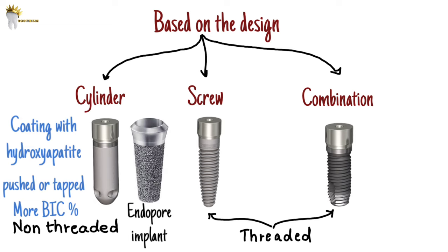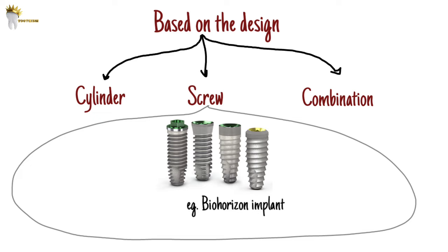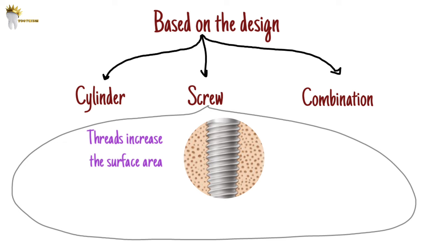The screw or threaded implant is the most commonly used design. The threads help in the retention of the implant in bone, and these are screwed into the prepared osteotomy site. Examples include BioHorizon implants and Nobel BioCare implants. This threaded design permits implant removal at the time of surgery if placement is not ideal, and also at stage 2 surgery if angulation or crestal bony contours are not correct. The threads are primarily designed to increase the bone-to-implant surface area and decrease stresses at the interface during occlusal loading compared with the cylinder implant body design, while also increasing mechanical retention in bone at initial implant insertion.